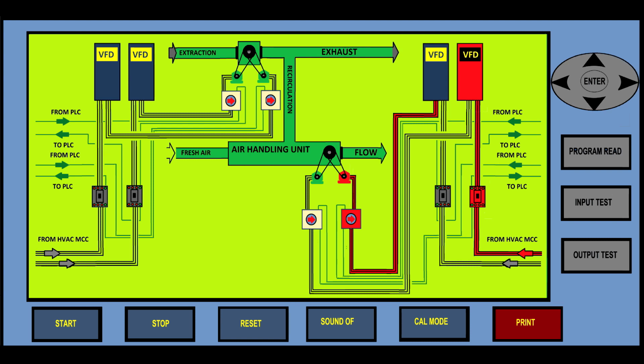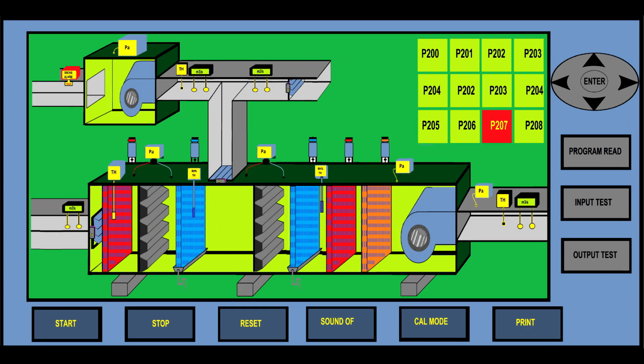So one motor has a problem with an electrical or mechanical failure, while the other one has a power supply problem. And again, on the next page, the HMI will have the capability to direct you to the right area to investigate this system correctly. So one motor has an electromechanical fault, whereas the other one is a power supply. You have to check the power supply from the MCC to the variable speed driver. And this is great because we'll cut a lot of time and this will be captured.